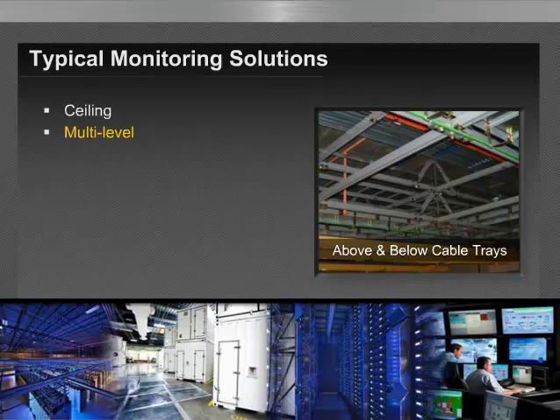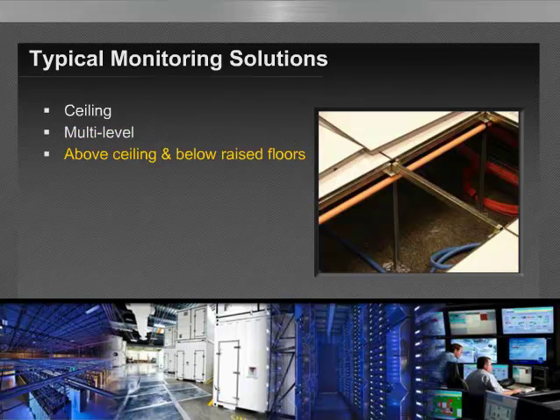Above ceiling and below raised floors, the idea that, again, trying to get to the detectors to maintain, test, and inspect them could be challenging using traditional means where the air velocities may be outside the range of the detectors. So the idea of utilizing an air sampling type system, or the convenience of accessing the detector in an accessible location, might be of concern.